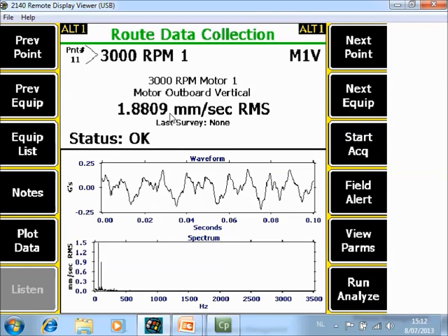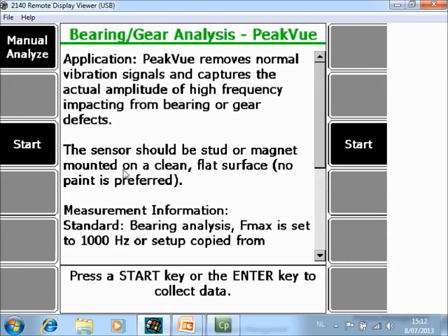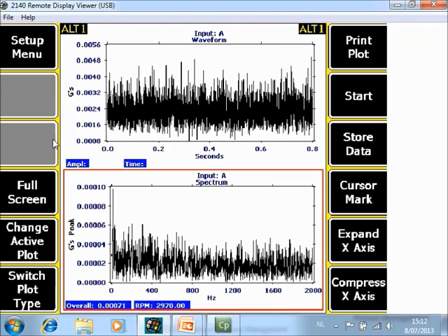If you want to collect for this point also PeakVue data and you have not specified it in the route mode — so you only want to collect an additional point with the PeakVue technology — an easy way to do it is to go to Run Analyze F12, then go to Bearing Gear Analysis Peak View F6, and press Start to begin data acquisition. It is already done — press Enter to view.